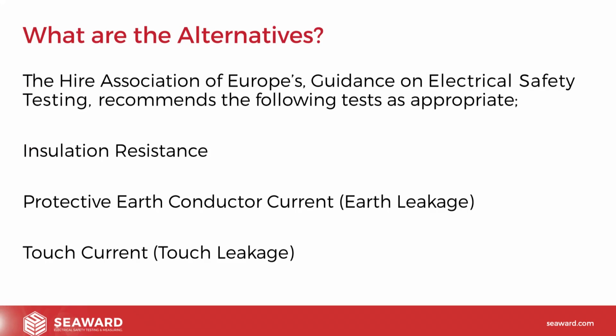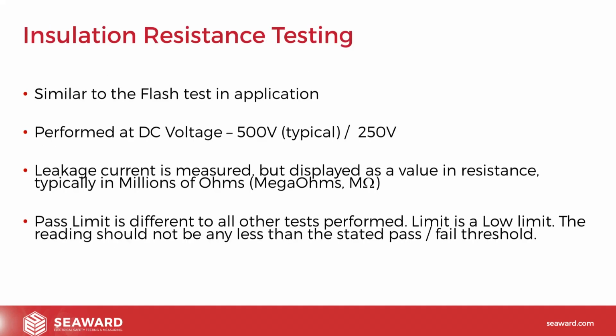According to the Hire Association Europe's guidance on electrical safety testing, their code of practice recommends the following tests as appropriate alternatives to the high voltage test. Firstly, we have insulation resistance testing. We have protective earth conductor current, or as it's more commonly known, earth leakage testing. And then we have our touch current test, or touch leakage, again, as it's commonly known. Throughout the presentation, we'll discuss which products are able to do certain tests. But let's move on and talk about the first test in the range, the insulation resistance test.